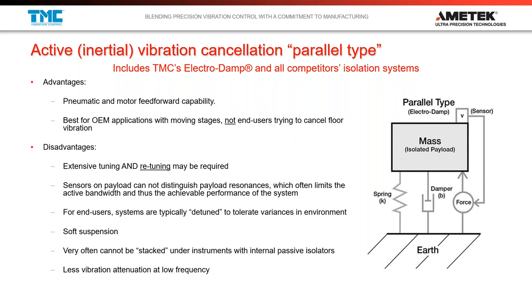In addition to that amplified vibration at low frequency, we're also getting in all of the other inputs from the system. So you've got acoustics on the payload, you've got the payload's own motion, maybe you've got some user motion on the payload, and at the same time you're trying to cancel, so the system doesn't know what to cancel. It's getting fed a lot of information, resonance from its own springs, and all the payload information. So you start to encounter bandwidth limitations, and you start to encounter limitations to how well the system can perform. And this starts to get you to a place where you're always kind of grappling with stability.